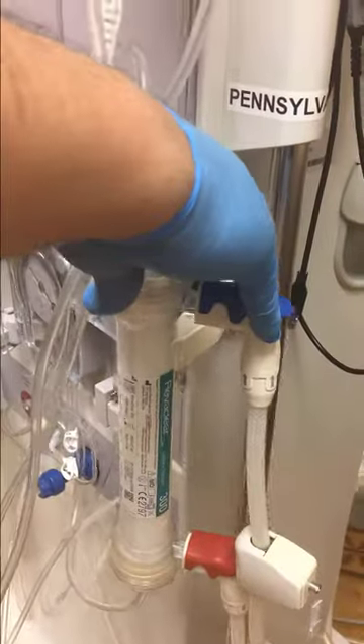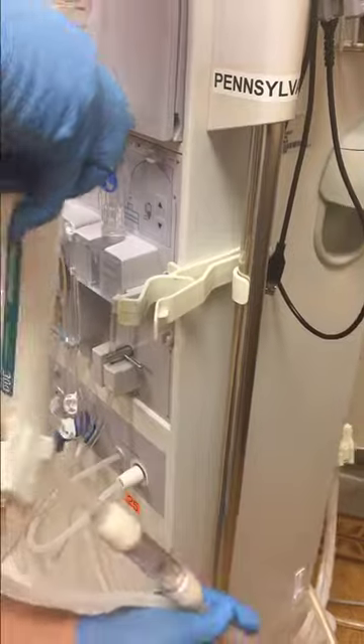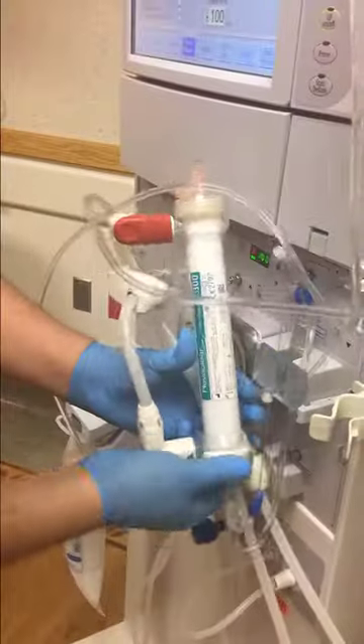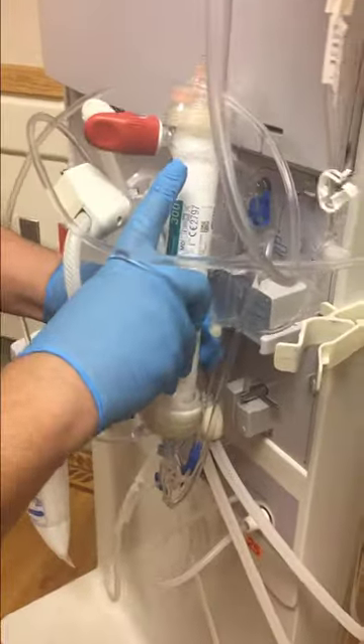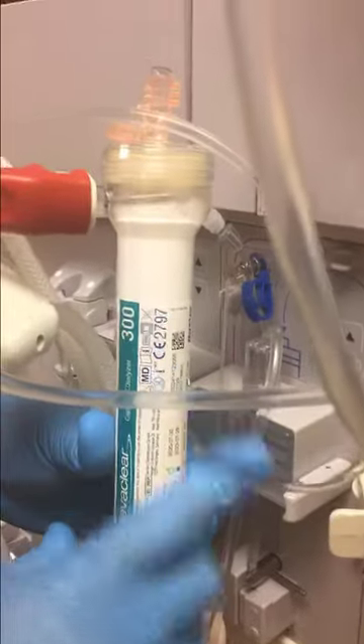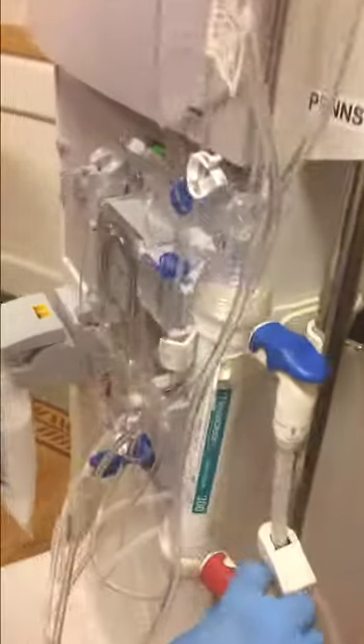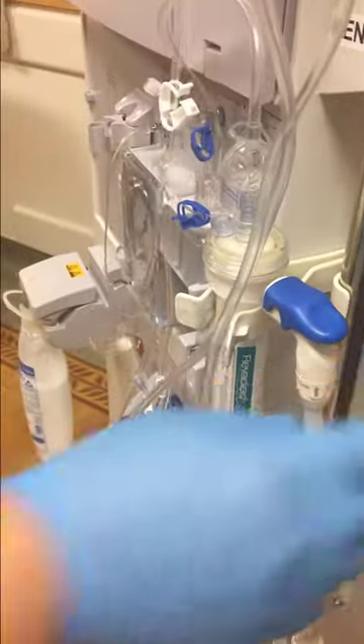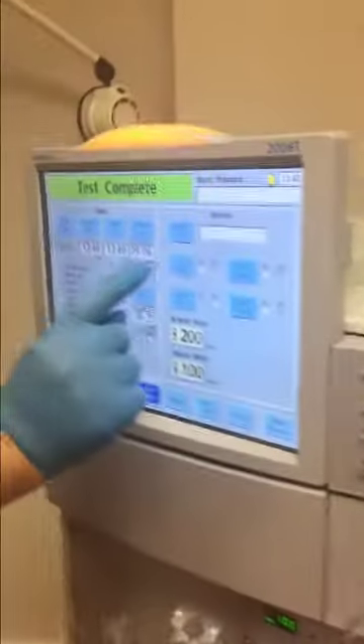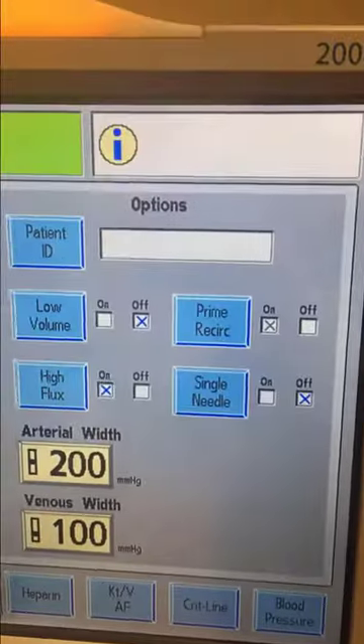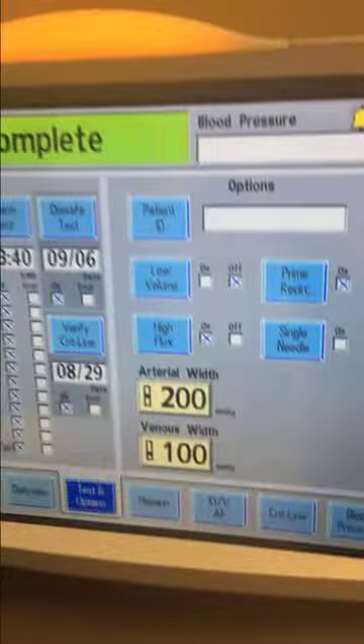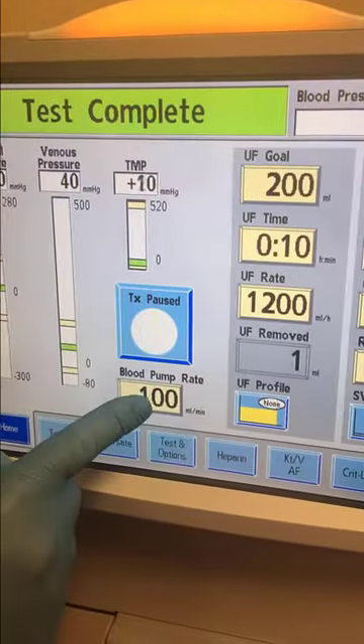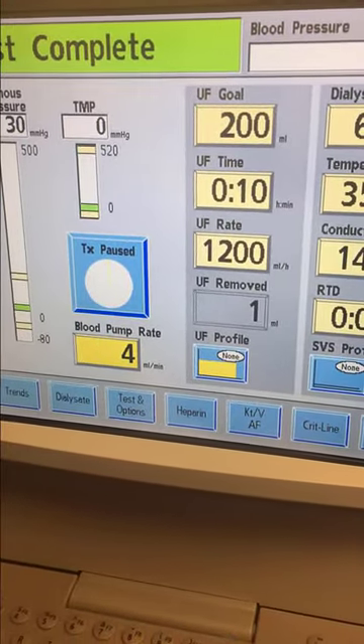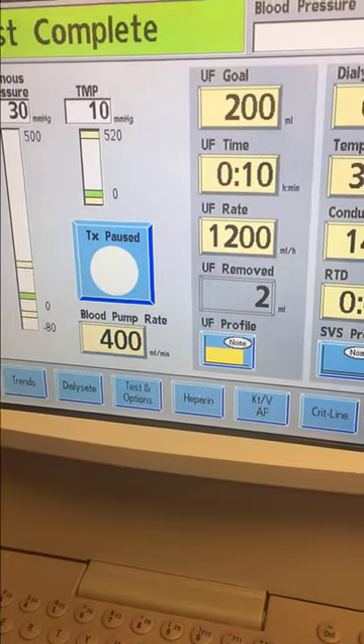So you'll see him turn this dialyzer in just a second to make sure that we force all of the air out of the dialyzer. And once it's full, he's just going to flip it back over the way it was and put it back in the holder. Now he's going to select prime recirculation and then enter or confirm. And that will set a preset volume of 200 milliliters and a UF time of 10 minutes.